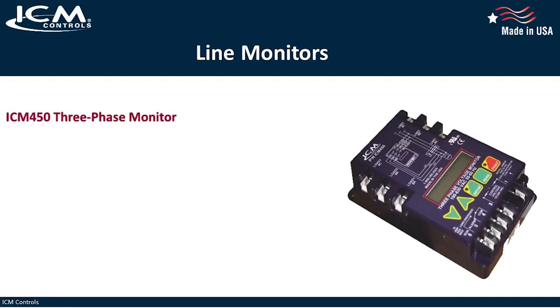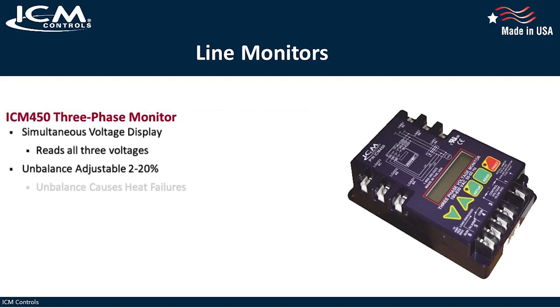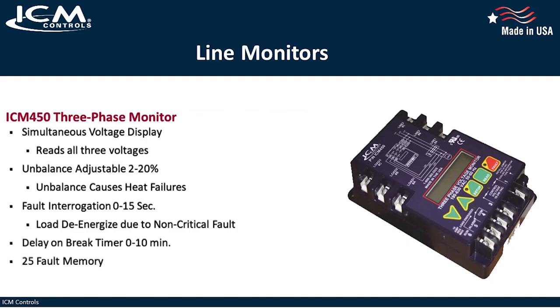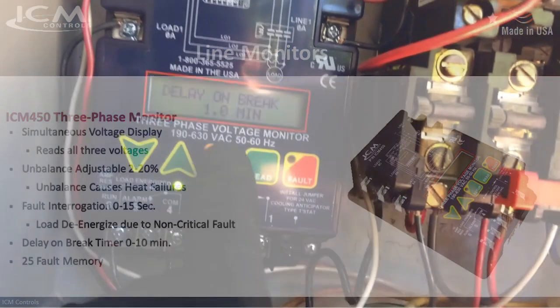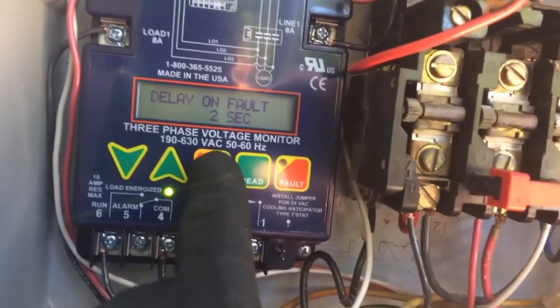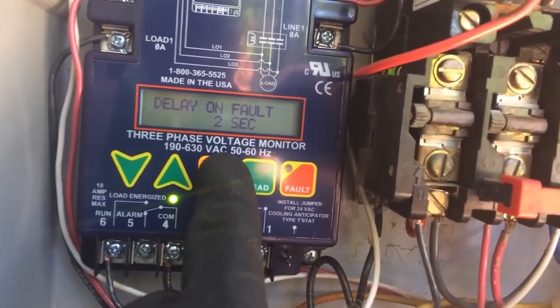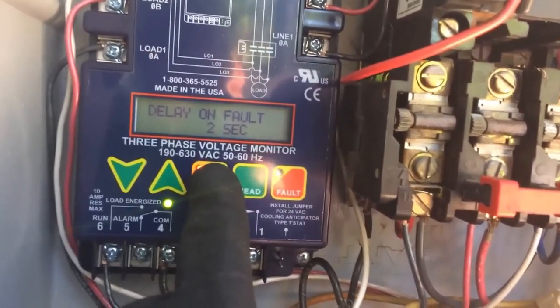Line voltage monitors, or phase monitors, are vital add-on investments that help protect your valuable equipment against voltage imbalance and other power anomalies, including high and low voltage, phase loss, phase reversal, rapid short cycling, and more. The better three-phase line voltage monitors on the market, like the ICM 450, are programmable and have digital displays that let you get real-time readouts of all three phases simultaneously. Plus, should a fault occur, the ICM 450 will record and save the last 25 faults, so you can get an idea of where to start looking for a problem when one occurs.